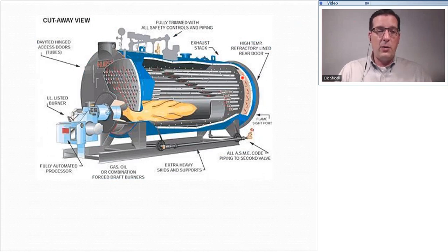So here's a cutaway diagram of a typical fire tube boiler. We see a power burner here shooting into a horizontal flame. This could be gas, this could be oil. This could also be a dual fuel type of burner that can utilize either gas or oil. And so fire goes in this way, runs into the back wall, takes a turn, and now we're talking strictly combustion products because the flame is only maybe 2 or 3 feet long. The rest of it is all hot gases from the combustion process moving through all of these different tubes. Comes back into the front, takes another turn out this way, and eventually makes its way out the flue. So that's a shell and tube or fire tube boiler.